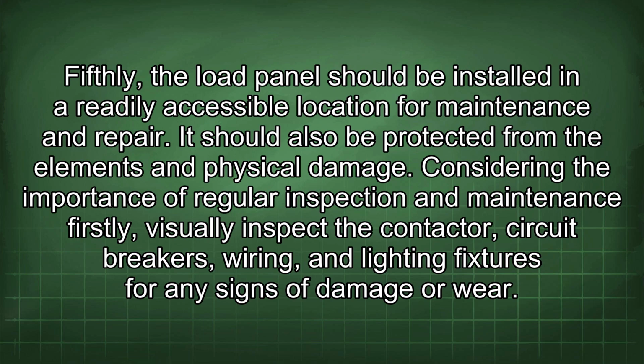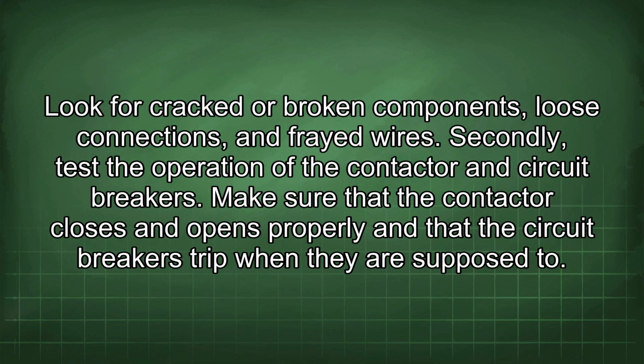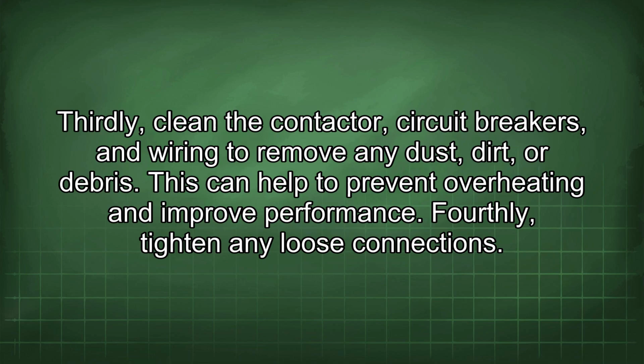Considering the importance of regular inspection and maintenance, firstly, visually inspect the contactor, circuit breakers, wiring, and lighting fixtures for any signs of damage or wear. Look for cracked or broken components, loose connections, and frayed wires. Secondly, test the operation of the contactor and circuit breakers. Make sure that the contactor closes and opens properly and that the circuit breakers trip when they are supposed to. Thirdly, clean the contactor, circuit breakers, and wiring to remove any dust, dirt, or debris. This can help to prevent overheating and improve performance.